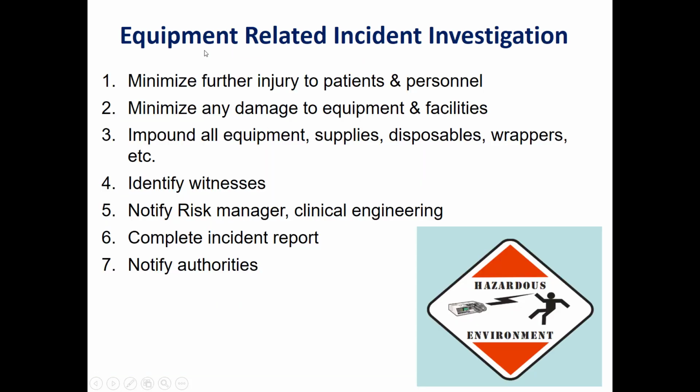Another policy and procedure is the equipment-related incident investigation. In case we have an incident that happened due to the use of a medical device, an incident investigation should be made in order to prevent the happening, or minimize the happening, of such an incident in the future, and consequently minimize further injury to the patients or staff, and also to prevent or minimize the damage to the equipment and facilities.